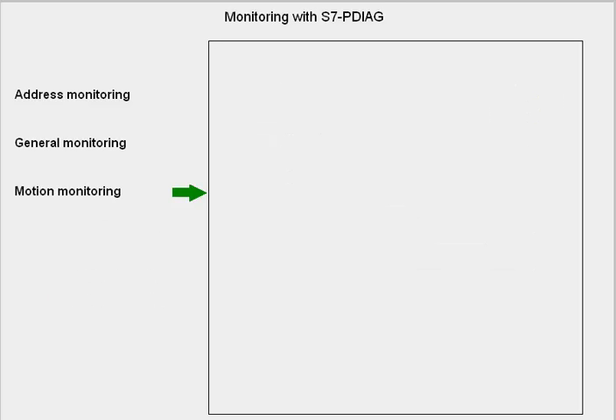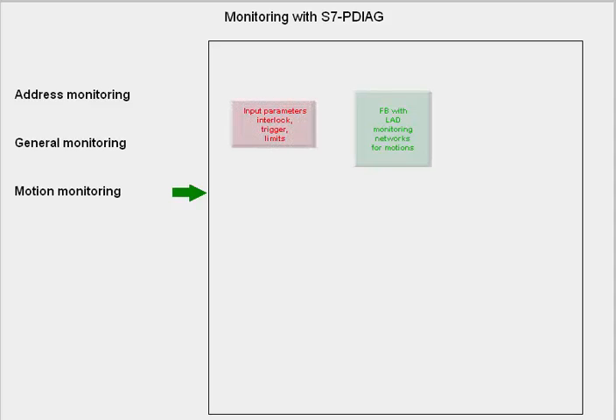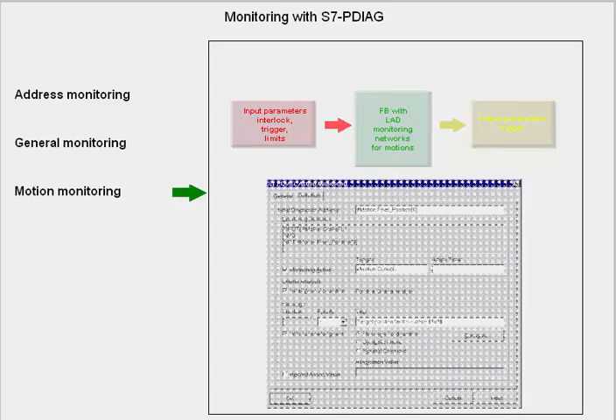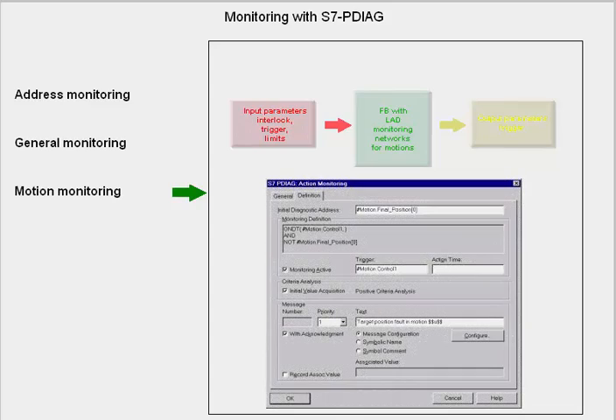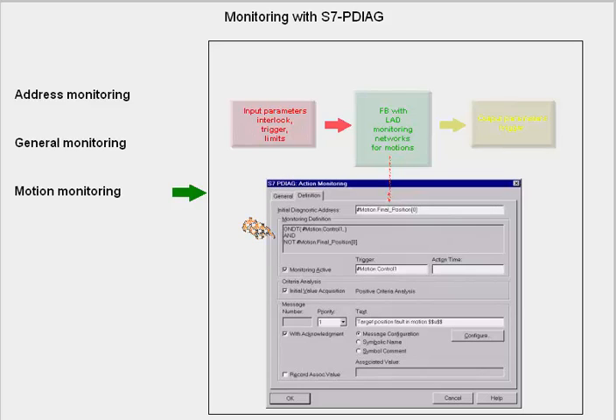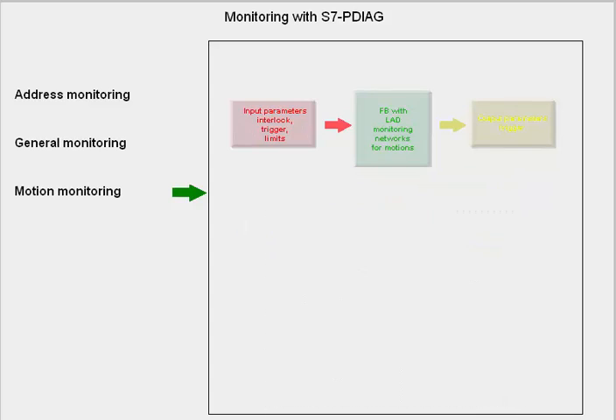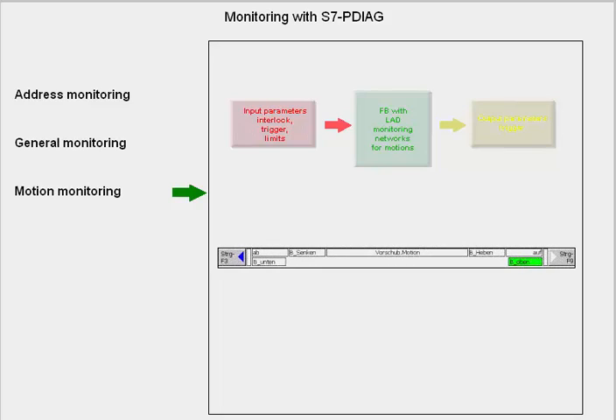Specific programming regulations have to be observed for the concept of movement monitoring. With S7-PDIAG functions, a block is supplied with standardized monitoring networks and it has to be linked via parameters with the application specific addresses. It already contains the necessary initial diagnostic addresses and data structures on which the configuration masks of the different movement monitoring types are set. All you have to do is assign the parameters to the marked initial diagnostic addresses using the configuration dialog provided. The monitoring logic is then generated by the system automatically for the motion monitoring concerned in each case. The standardized data structures make it possible to incorporate ready-made HMI masks such as the manual operation mask without having to do any programming.